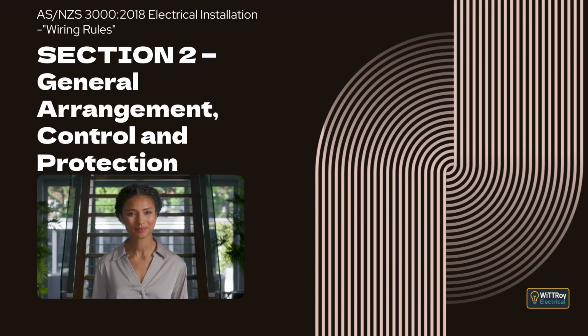For transformers, we use similar ideas: strong insulation between windings, or a conductive screen that is earthed, so any fault energy is safely carried away and the supply disconnects if needed. Transformer windings that operate at different voltages must be clearly separated. If a fault does occur inside a transformer, the design must make sure that the protective device will disconnect the supply quickly.